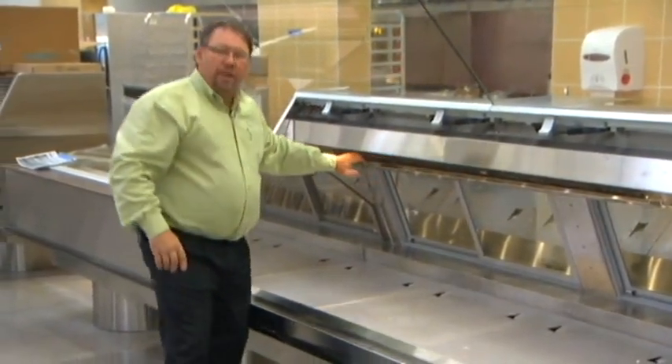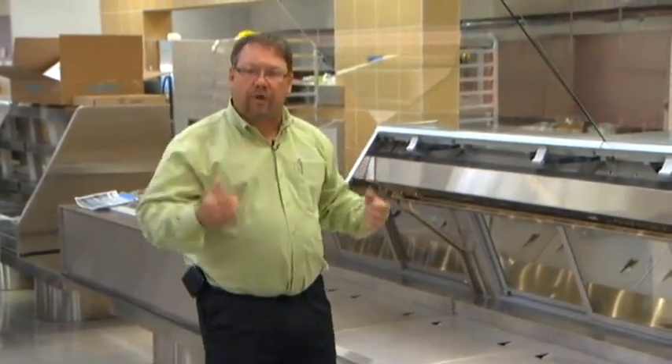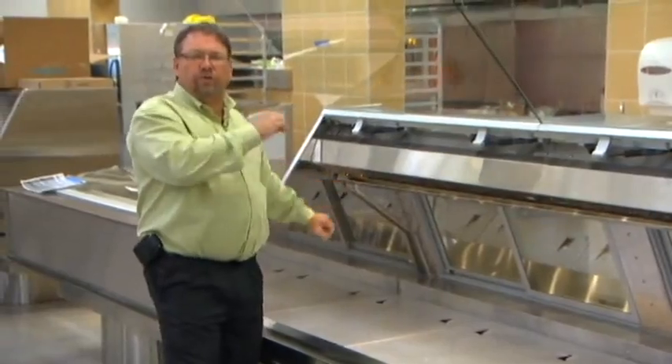We need to check and ensure that we have plenty of pitch coming down toward the drain end, and that our drain remains clear. We don't want to reach a point where we're overfilling that drain and putting water on top of the product. Make sure the drain runs clear and is free of obstructions and debris, and you'll have a perfectly drained system that works fine. I'm Rusty Walker, and that's your tech day.